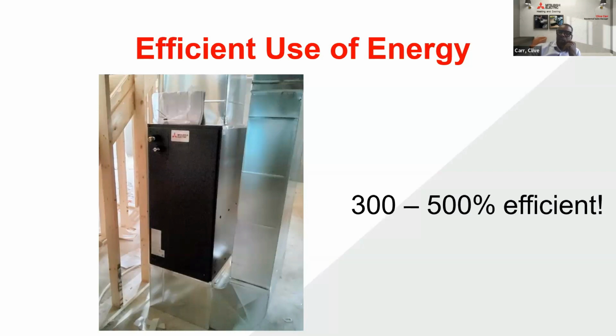Mitsubishi Electric has been able to revolutionize the concept of air source heat pump, therefore debunking quite a bit of the stigma that is associated with air source heat pump technology. The technology itself, yes, that factor still remains: as the outside temperature goes down, the heating capacity reduces and the efficiency reduces. But the rate at which you reduce that heating capacity and efficiency is what plays a big part.